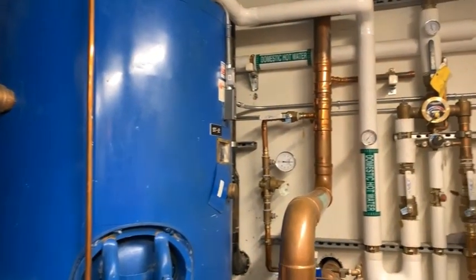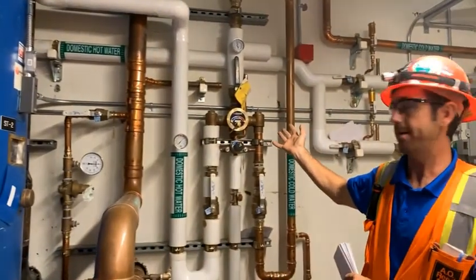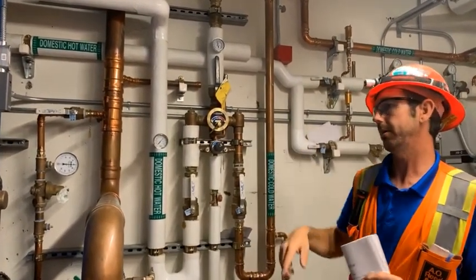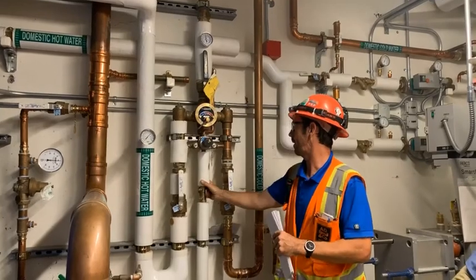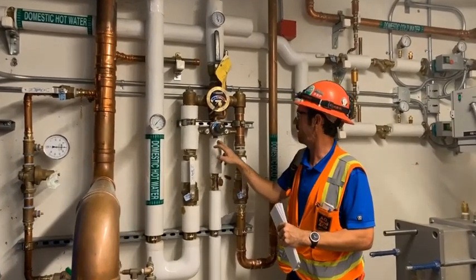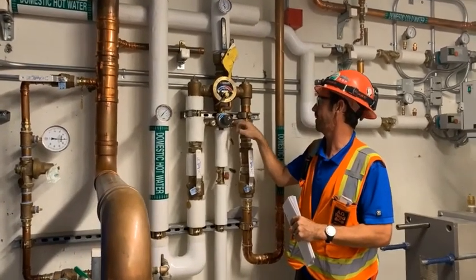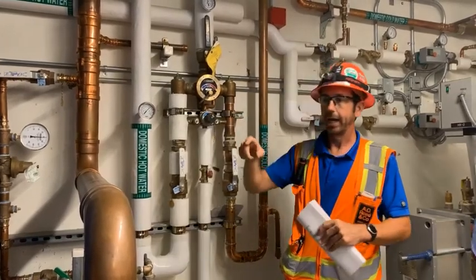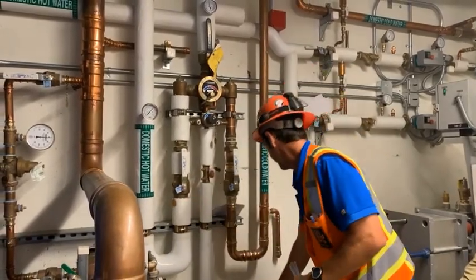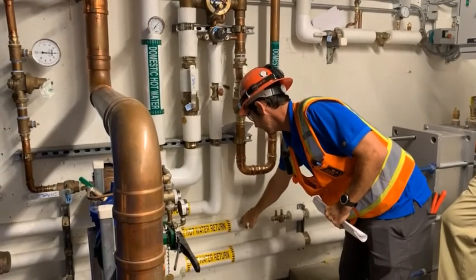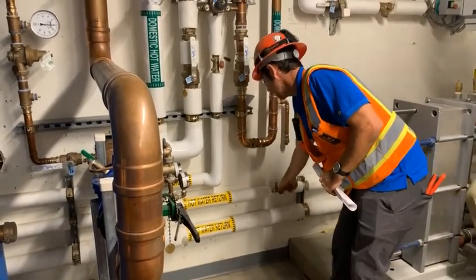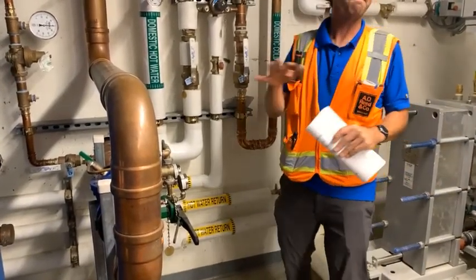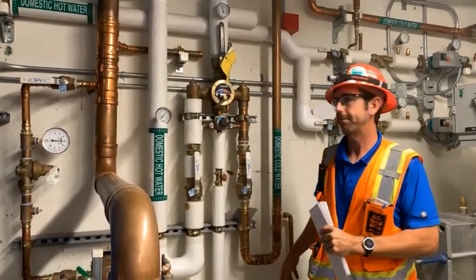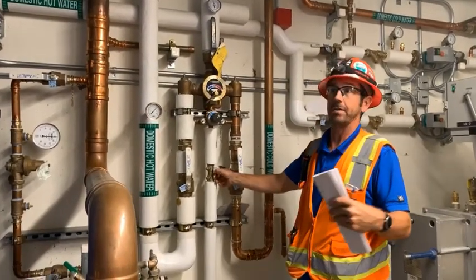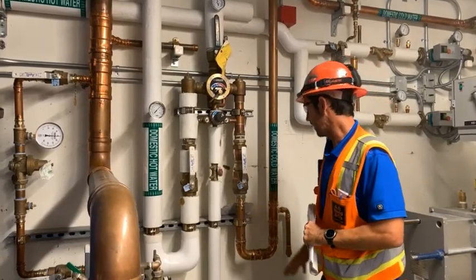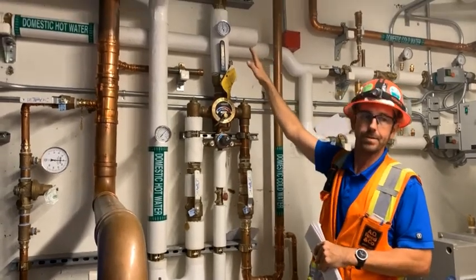This is all just part of how the mixing valve works. That's why I'm explaining it right now. So in that hot water return loop, we have like 80% of the flow that will run through this line right here into the main mixing chamber of the valve and out. In part of that loop, if we followed it all the way out, that'll be this line right here too. This is part of the return loop. We have another circuit setter here. During no flow conditions, I've already fine tuned the circuit setters to give us a constant 120 degree outlet temperature, okay?